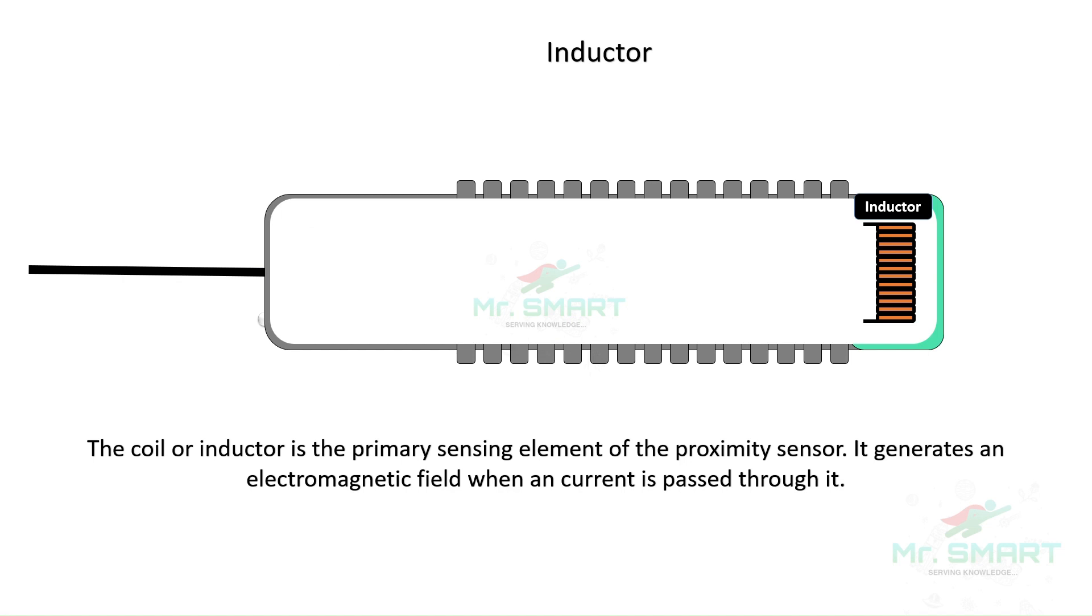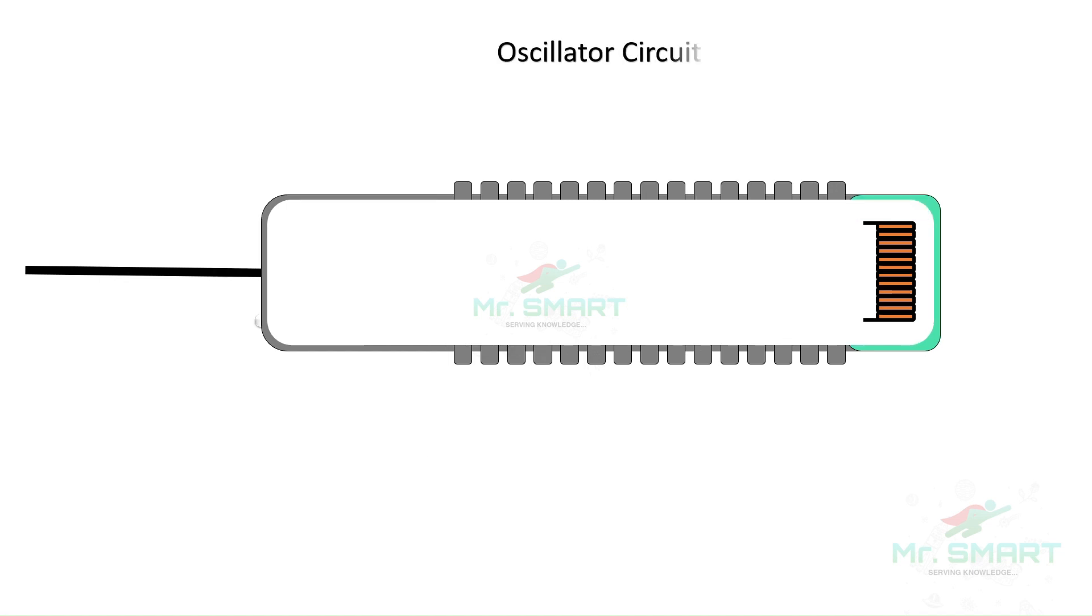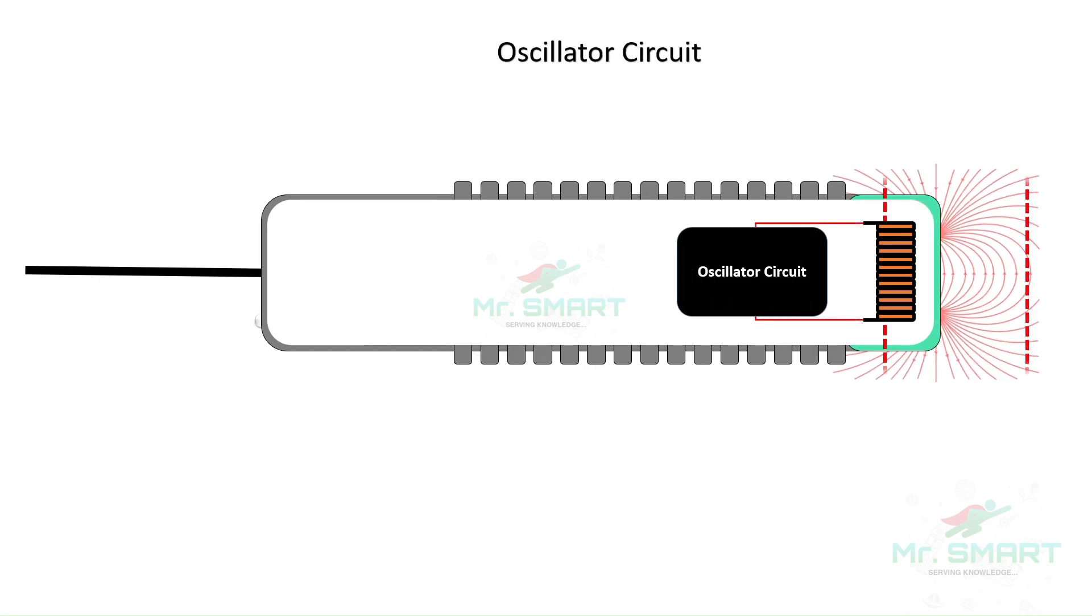It generates an electromagnetic field when current is passed through it. It is connected to a unit called an oscillator circuit. The oscillator circuit generates the current that powers the coil or inductor. When an electrical current is applied to the inductor, they create an electromagnetic field that extends outward from the sensor's active face and forms a sensing area.